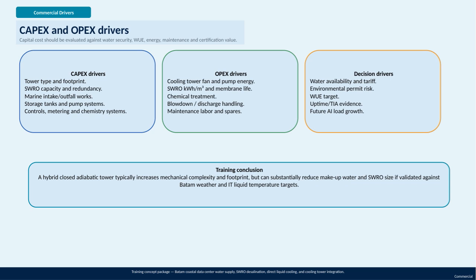Specifically, CAPEX drivers include things like the type of cooling tower selected and its footprint, the capacity and redundancy of the seawater reverse osmosis or SWRO system, the marine intake and outfall works, as well as storage tanks, pump systems, and the necessary control, metering, and chemistry monitoring systems. On the operational side, or OPEX, the main costs stem from the energy needed to run cooling tower fans and pumps, the electricity used per cubic meter of water treated by the SWRO system, membrane life, chemical treatment requirements, handling of blowdown and discharge, and maintenance labor and spare parts.